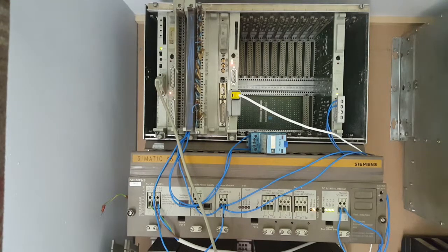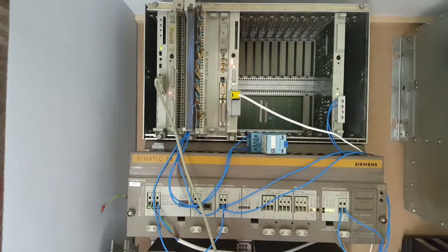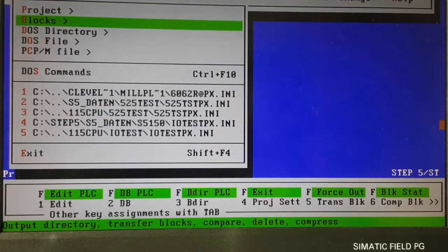Now, as this is a new installation, both the run and stop LED will remain illuminated. This indicates that the synchronization will need to be carried out. This means that the card now needs to be synchronized to the CPU. To configure the card, you will need a 6ES5734 programming lead. This is the same one as used for programming the CPU. You will also need SINEC NCM installed on the same PC as the Step 5 programming package.